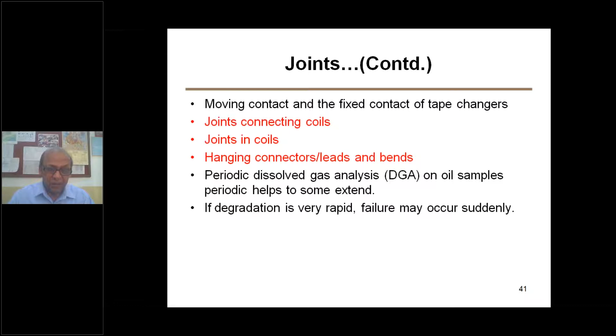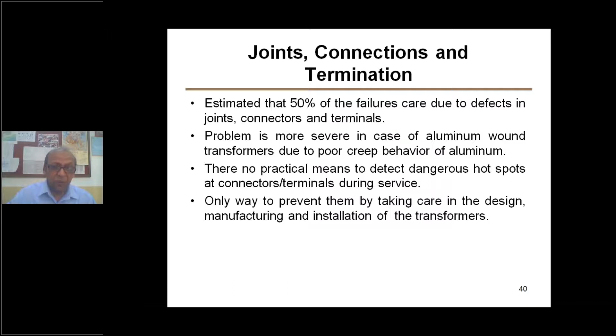That is what we observe during the warranty period. When there are failures, it means somewhere there must be a manufacturing defect. Also, during operation, there are serious issues in Indian conditions. You have abnormal transients, sustained abnormal operation of the transformer, which abuses it. The transformer is subjected to sun, and that causes an unnecessary increase in temperature of the transformer by 15 to 20 degrees centigrade for no reason.